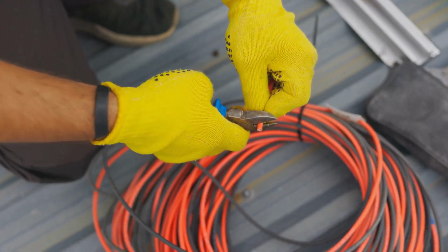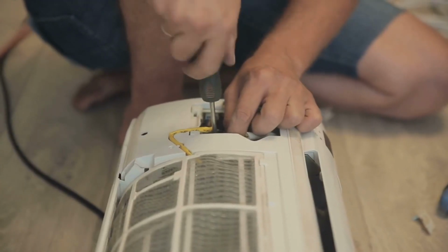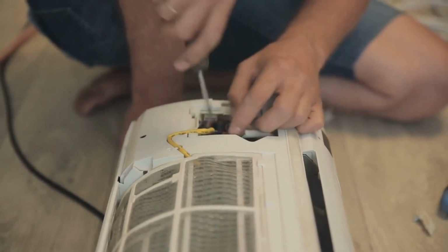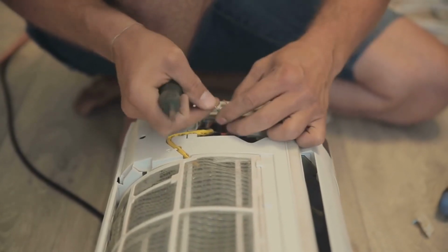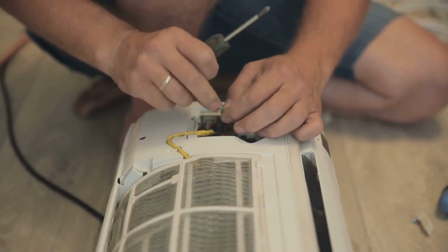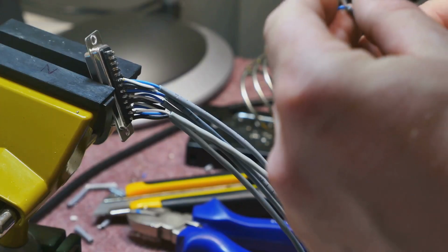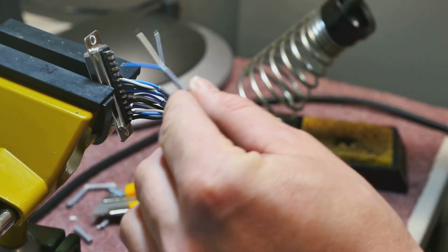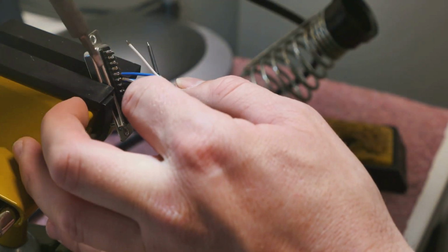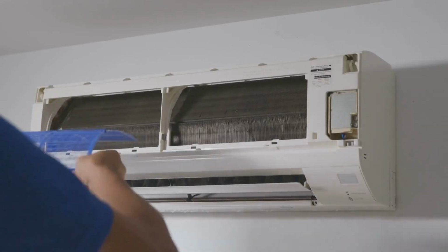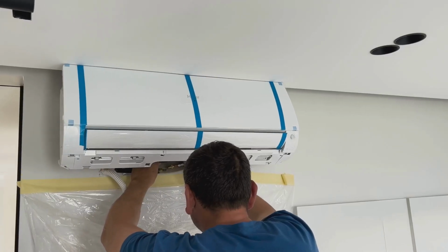Next, connect the electrical wiring. Carefully connect the electrical wiring from the AC unit to the electrical supply, following the manufacturer's instructions and of course local electrical codes. Use wire strippers to expose the wire ends and connect them securely using wire nuts. Now hang the indoor unit. Lift the indoor unit and carefully hook it onto the mounting plate. Ensure the unit is securely in place and level. This part is super important.